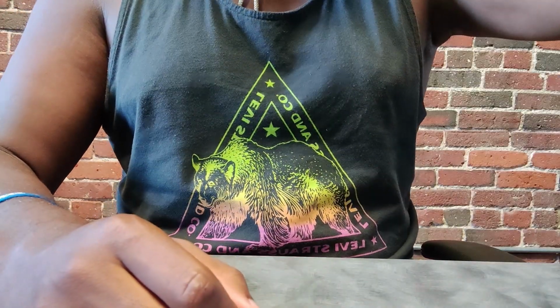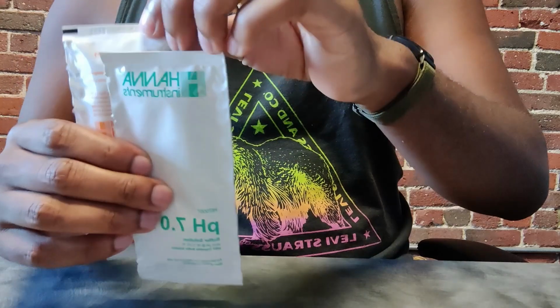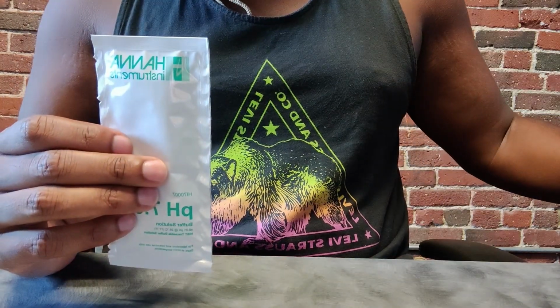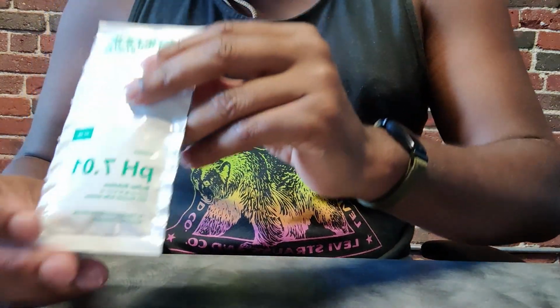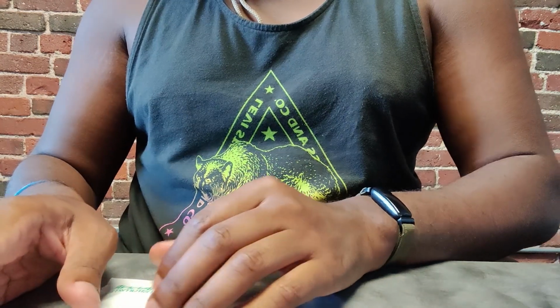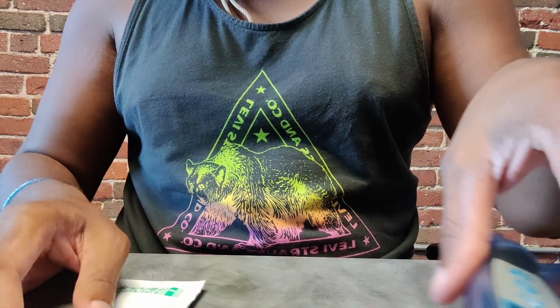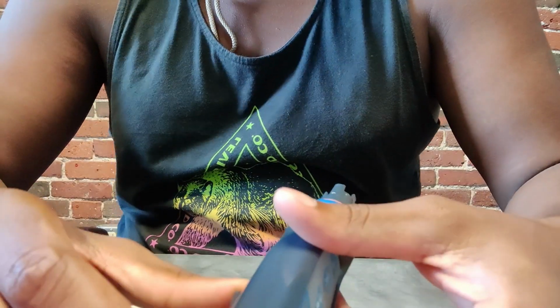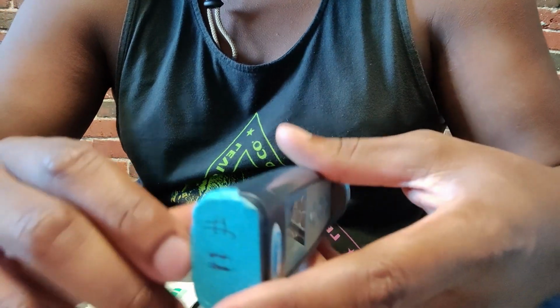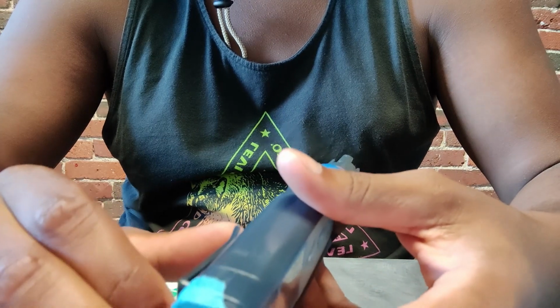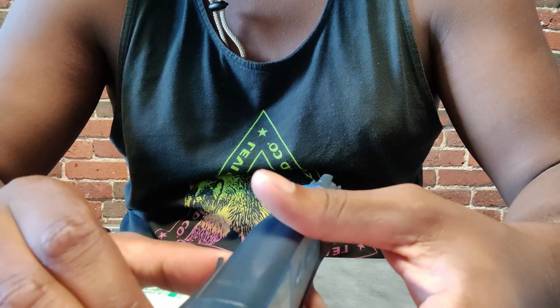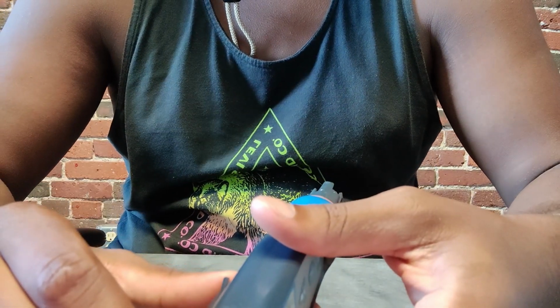Grab your packets and put aside the orange one for now. Both of these packets contain the calibration standards that you need to calibrate your machine, and can both go down your drain when the calibration process is complete. There should be enough fluid in both of those to last you 2 calibration cycles. If you ever need more, you can come by the office to pick them up after a sampling, or anytime during the week.